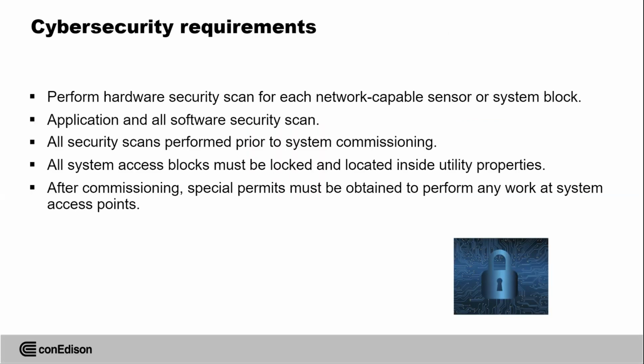So cybersecurity requirements, that was a very robust set of requirements for our system. We perform a hardware security scan for each network component and for each sensor. For each processor, we perform a cybersecurity check. Then application and software security scans. All security scans are performed prior to system commissioning. After every single component has been checked, now you check the entire system, you check all the ports.